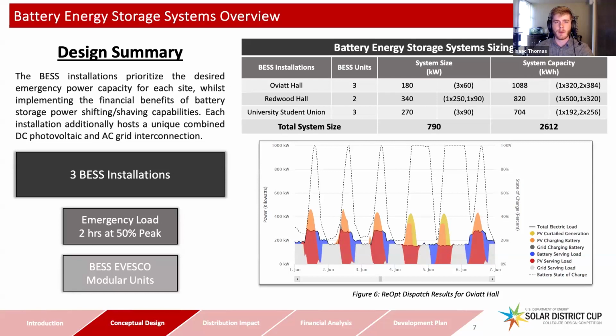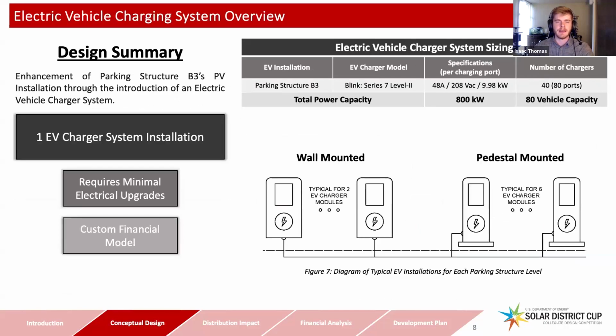Our 1 EV charging system is an enhancement of parking structure B3's photovoltaic design, meaning it requires minimal electrical upgrades. One challenge we faced was that the Solar District Cup doesn't necessarily include EV chargers, so we had to create a custom financial model for the system. The final design implements 40 level 2 EV chargers. At 2 ports per charger, this gives us an 80 vehicle capacity and 800 kilowatts of total power output.